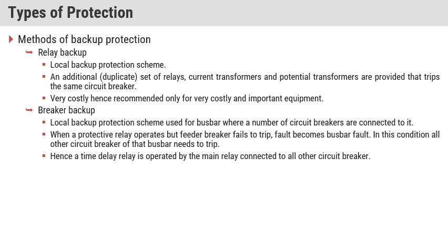Another one is breaker backup, a local backup protection scheme used for a bus bar where a number of circuit breakers are connected to it. When a protective relay operates but the feeder breaker fails to trip, the fault becomes a bus bar fault. In this condition, all other circuit breakers of that bus bar need to trip. Hence a time delay relay, operated by the main relay, is connected to all other circuit breakers.